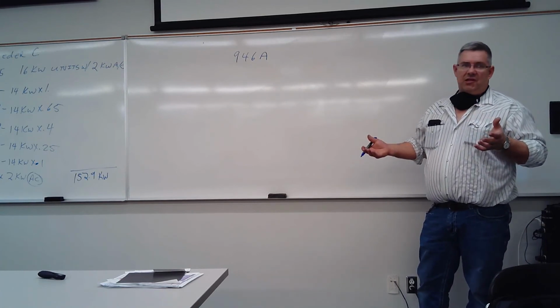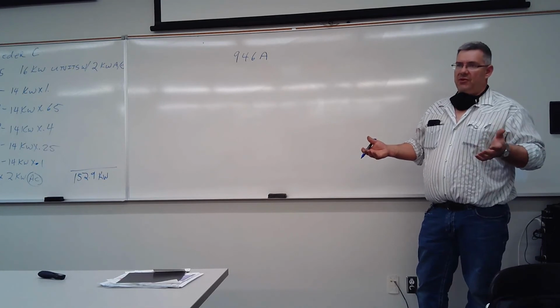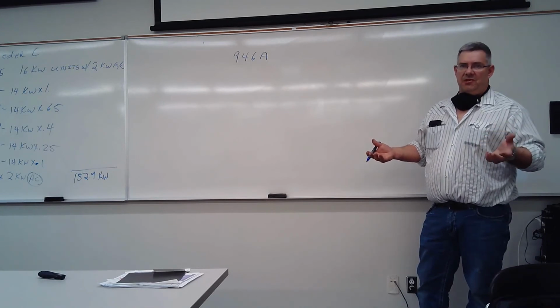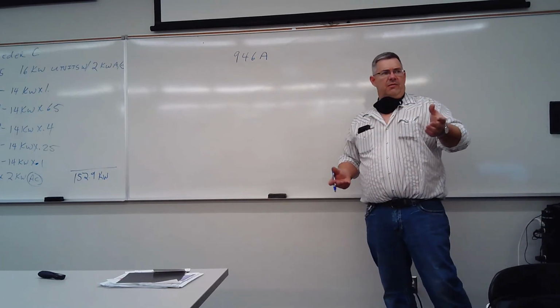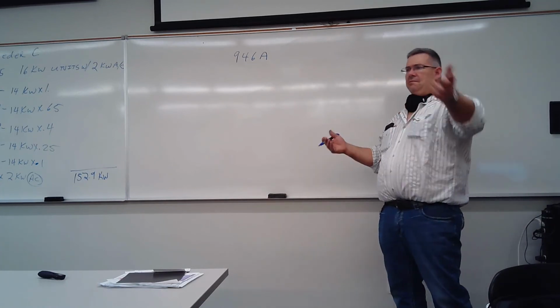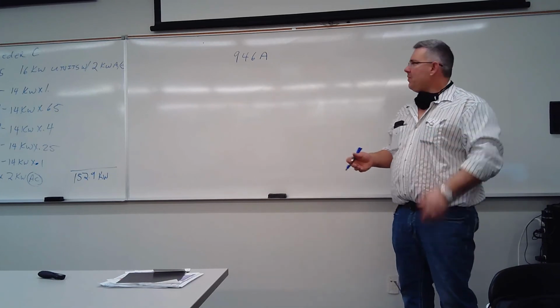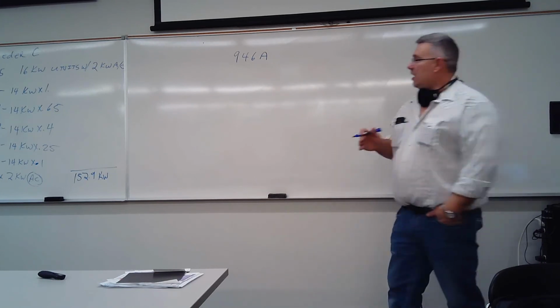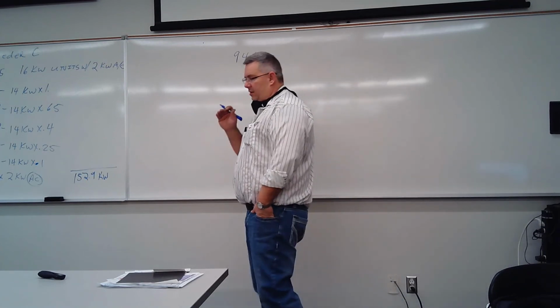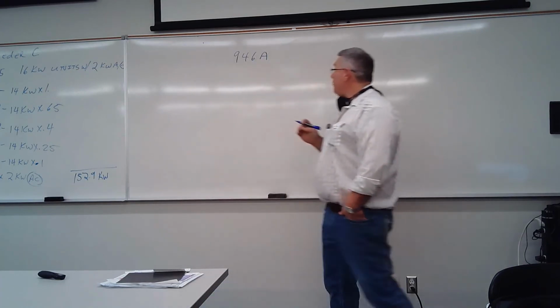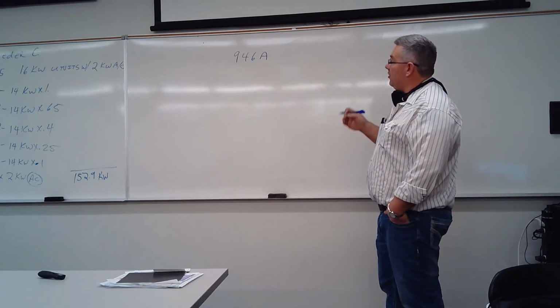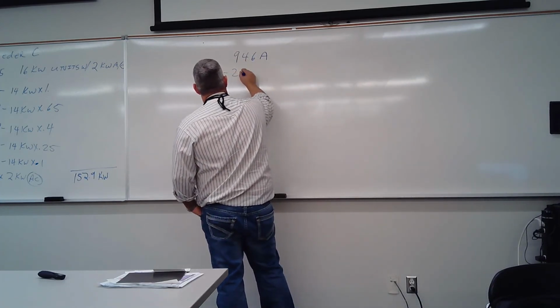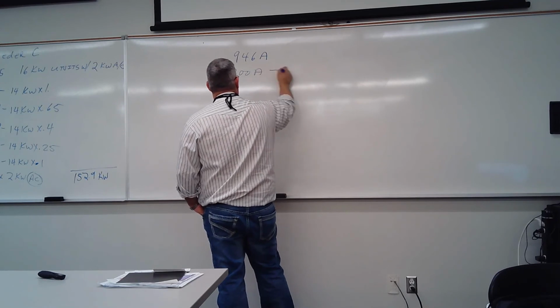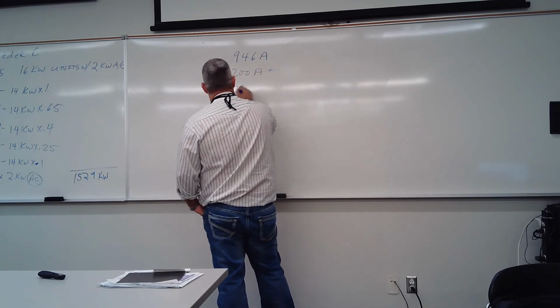The load on your neutral is going to be quite a bit less, right? If everything was perfectly balanced, the load on those neutral conductors would be zero. So why are we pulling 1,000 amps worth of neutral conductor when it's going to have 200 amps on it or something, right? So you're allowed to reduce the size of the neutral. And when you go through 4-018, it says you can reduce the size of neutral, anything over 200 amps. So the first thing you do with that 946 is you take out 200 amps. So that gives us 746.